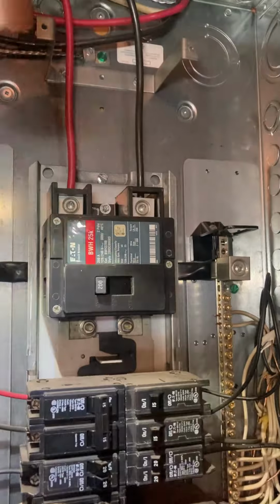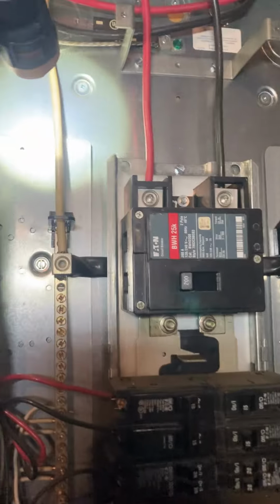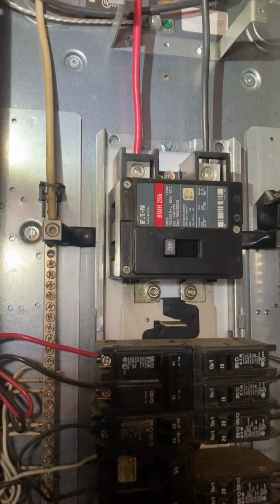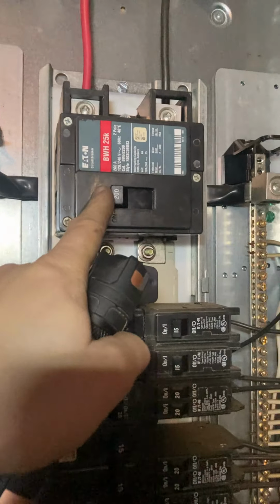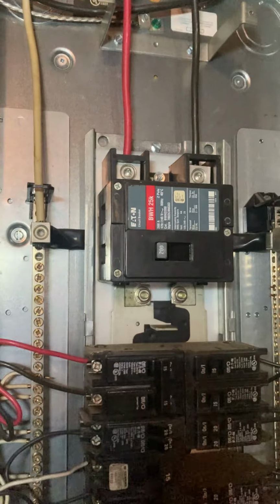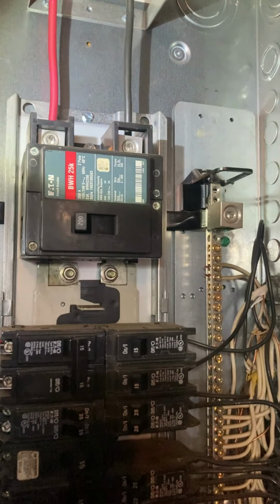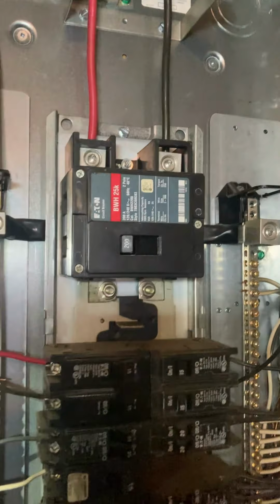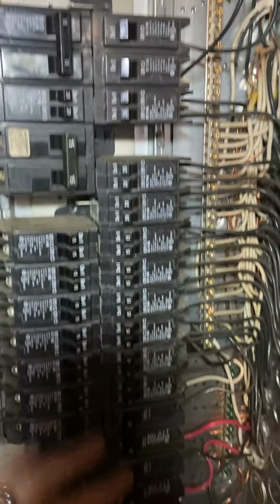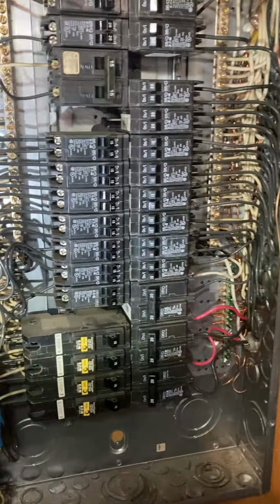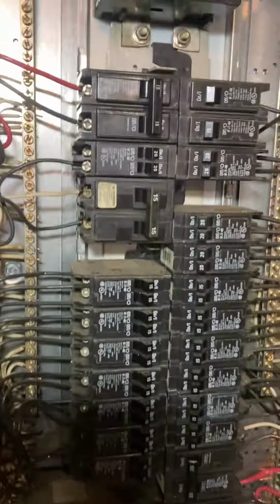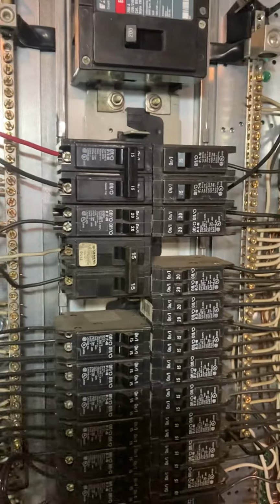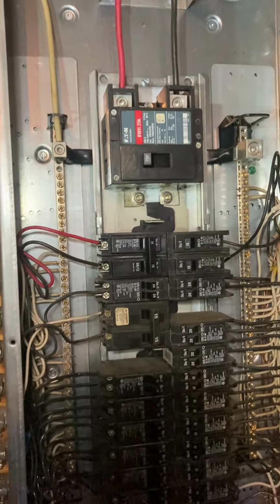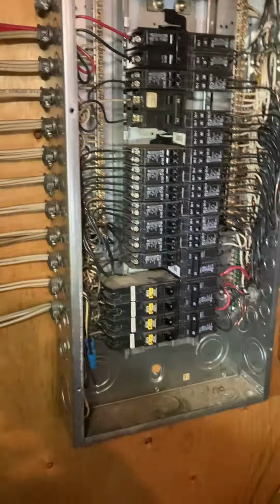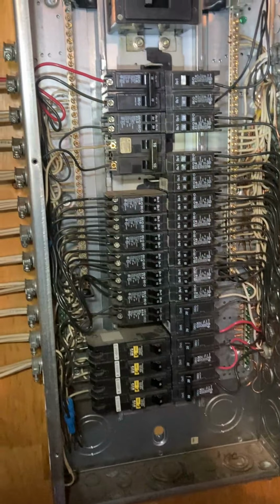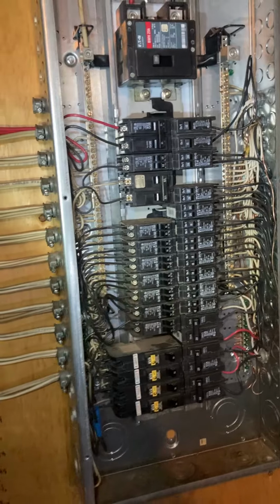These 2 wires up here, the red and black, and this neutral line, are coming from the grid, and they cannot be shut off by turning this big breaker off. So the danger is these are always live unless your power's out. If you turn your main breaker off, all this stuff is dead, and that's recommended for this install, because you don't want to be playing around in here and accidentally touch something you shouldn't and end up dead. So if you're not comfortable with electronics or electricity, this is not your forte. Get someone to do it, and we offer this to people.